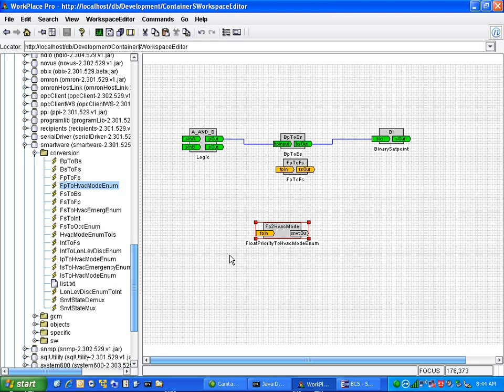You're limited. So we had to make use of every possible LON object there was. And then there were also the third-party devices like Trane chillers and boilers and things like that, which were LON devices where they had structured SNVTs that were unique just to the manufacturer. So we would often have to create objects to be able to link to them and send data back and forth. Whenever you see something similar to this, and you'll see others as we go down, they're very specific to LON controllers.